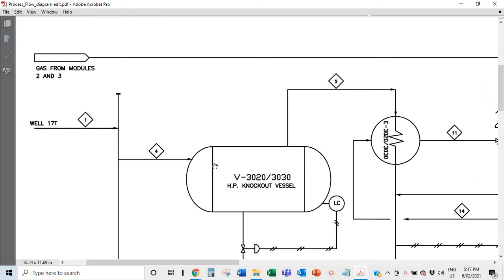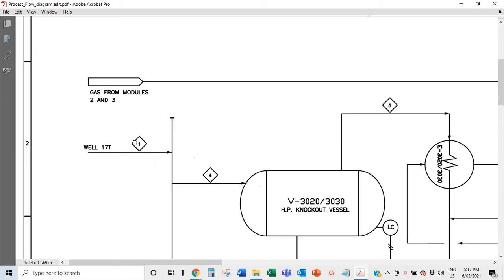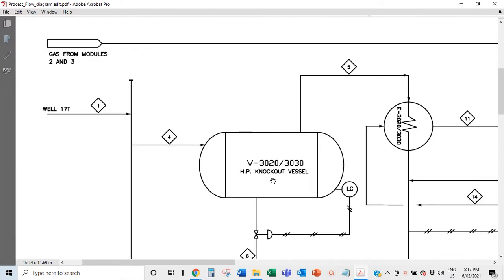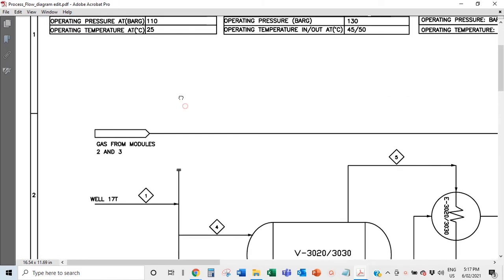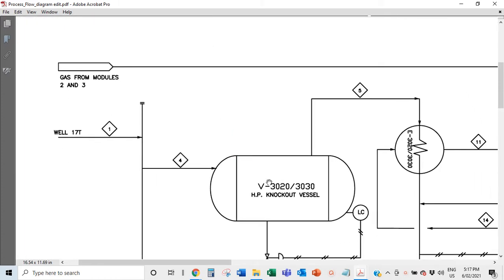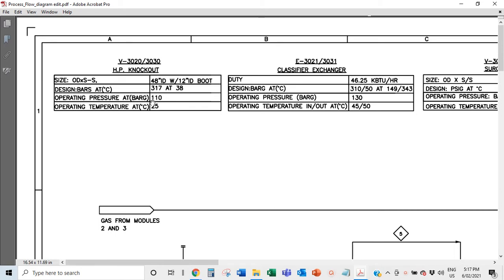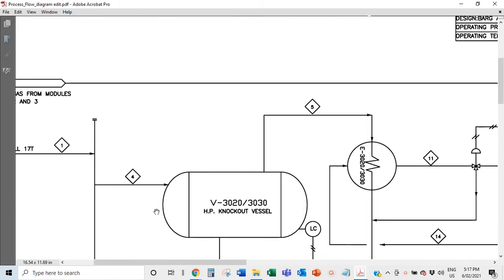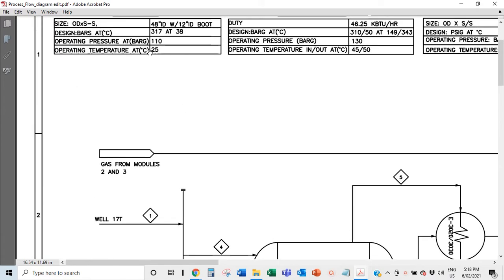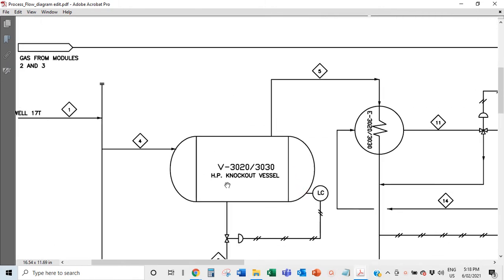You never want to hit the design pressure. If the well is coming in at 400 bar or even 318–319 bar, you would damage the vessel. The design handles emergencies, but the operating pressure is 110 bar — that's what it should be running at on a normal day. The operating temperature should be 25 degrees; anything above that may indicate a process upset.